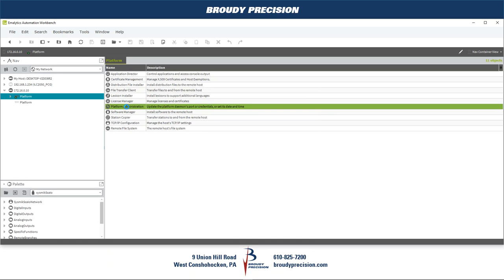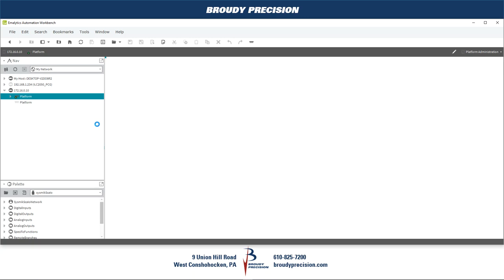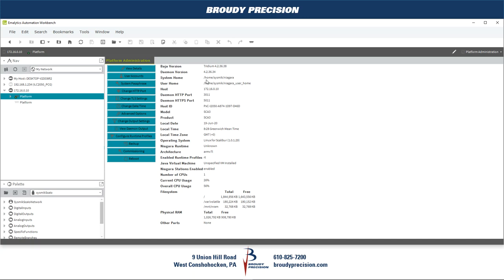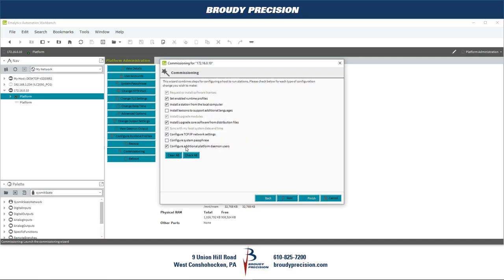At this point we're able to go to Platform Administration and commission the controller. When it reverted to factory defaults it went back to version 4.2, so during commissioning it will install the core software for the current version of Niagara. Follow through with commissioning, making sure you have your license file and station. That was everything to cover today — thank you for your time, thank you for your business, we do appreciate you, and have a great day.